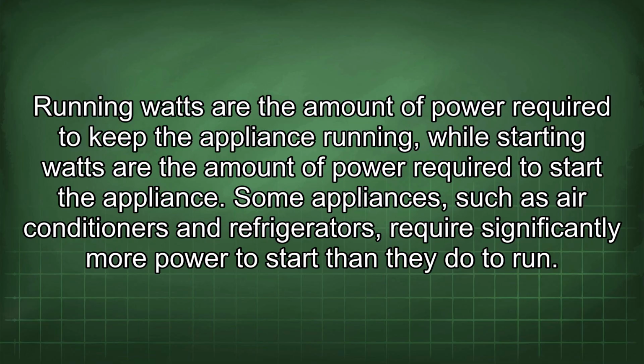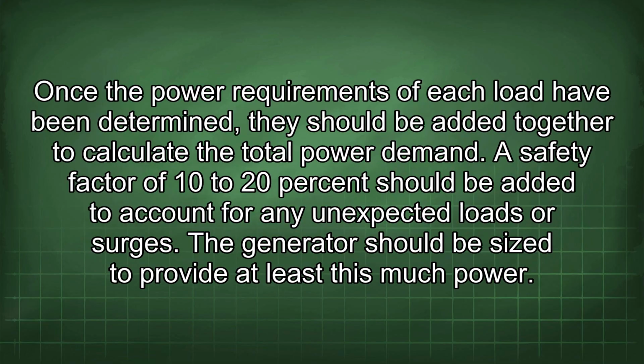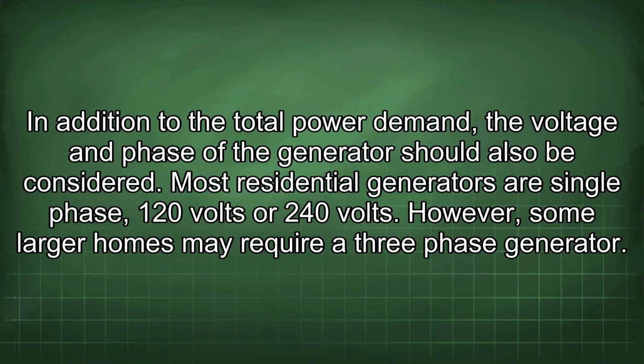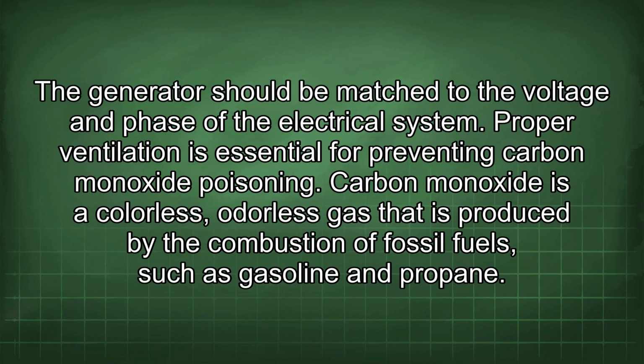Some appliances, such as air conditioners and refrigerators, require significantly more power to start than they do to run. Once the power requirements of each load have been determined, they should be added together to calculate the total power demand. A safety factor of 10 to 20% should be added to account for any unexpected loads or surges. The generator should be sized to provide at least this much power. In addition to the total power demand, the voltage and phase of the generator should also be considered. Most residential generators are single-phase, 120 volts or 240 volts. However, some larger homes may require a three-phase generator. The generator should be matched to the voltage and phase of the electrical system.